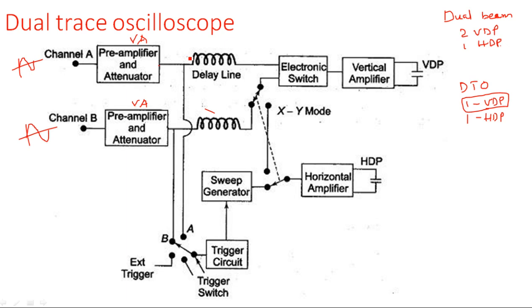The output of the pre-amplifier before being applied to the vertical deflection plates must pass through a delay line. This delay line is present for both channels. The purpose of the delay line is to hold the signal at the vertical plates until the horizontal deflection system is ready. The horizontal system involves three stages: trigger pulse generator, sweep generator, and horizontal amplifier — which takes longer than the vertical amplifier path alone.